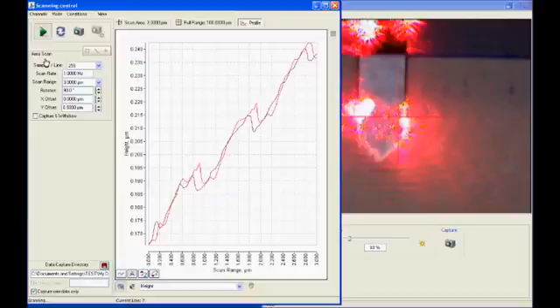The scan rate sets the speed at which the tip travels over the surface. With a scan range of 3 microns and a scan rate of 1 Hz, this means that the tip will travel 3 microns down and 3 microns back in 1 second. So our tip is traveling the surface at 6 microns per second. Never let the tip travel faster than 20 microns per second. Not only will this lead to inferior images, it will shorten the life of your tip.